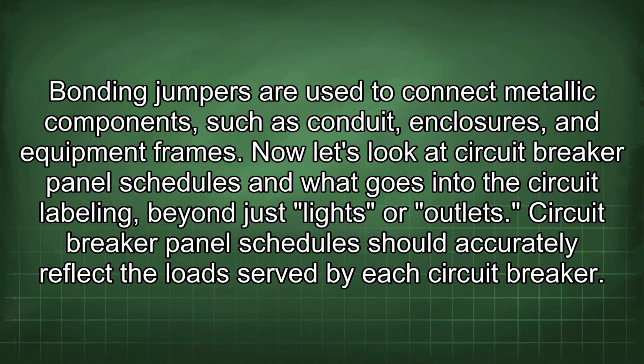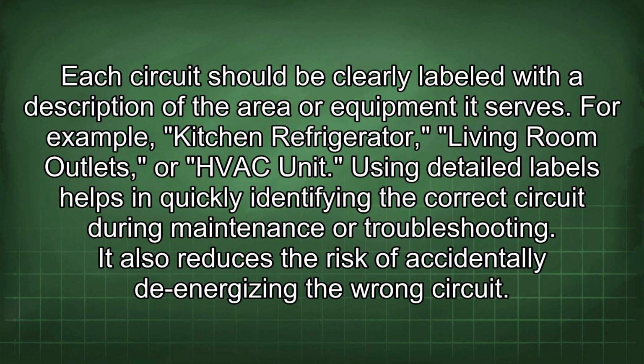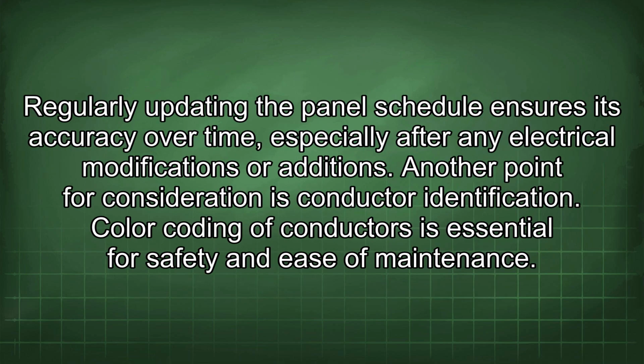Now let's look at circuit breaker panel schedules and what goes into the circuit labeling, beyond just lights or outlets. Circuit breaker panel schedule should accurately reflect the loads served by each circuit breaker. Each circuit should be clearly labeled with a description of the area or equipment it serves. For example, kitchen refrigerator, living room outlets, or HVAC unit. Using detailed labels helps in quickly identifying the correct circuit during maintenance or troubleshooting. It also reduces the risk of accidentally de-energizing the wrong circuit. Regularly updating the panel schedule ensures its accuracy over time, especially after any electrical modifications or additions.